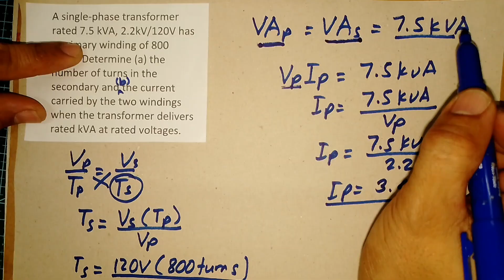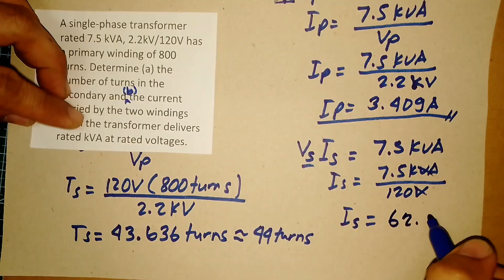Next, the volt-ampere of the secondary equals 7.5 kVA. So that gives us voltage of the secondary multiplied by the current of the secondary equals 7.5 kVA. Let's cross-multiply the voltage of the secondary. We have 7.5 kVA divided by 120 volts. So the voltage cancels out, leaving only amperes. Let's remember that 7.5 kVA is equivalent to 7,500, since some get confused about this. The answer here is 62.5 amperes.